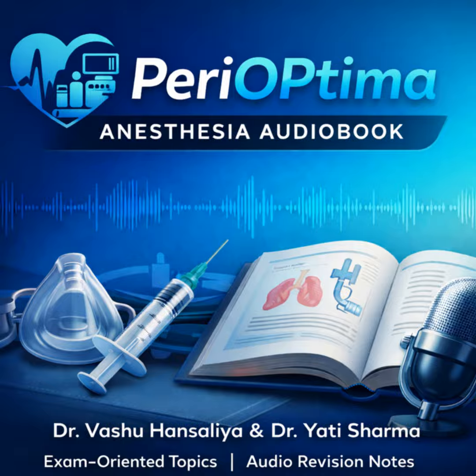They do. It's bulky, it's heavy, and it has numerous components: valves, an absorber that can fail. The large internal volume means changes in anesthetic depth, so wash in and wash out, are slower than in a low-volume Mapleson system. And the biggest one is the safety risk. The consequences of component failure, like an exhausted absorbent or stuck valves, are immediate and potentially catastrophic hypercapnia. That's a major point for examiners.